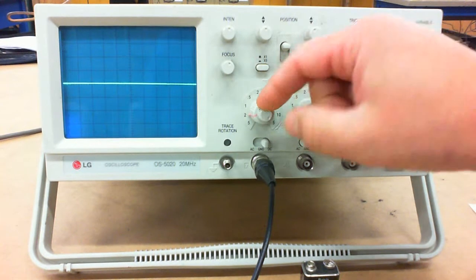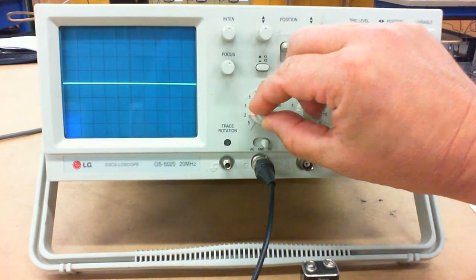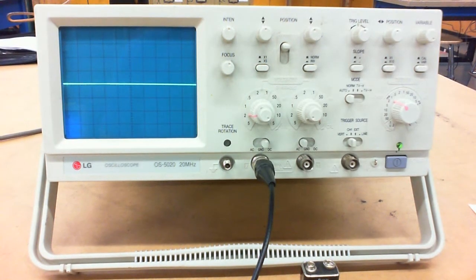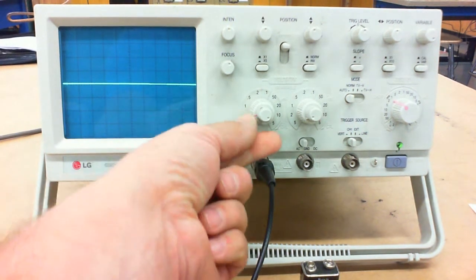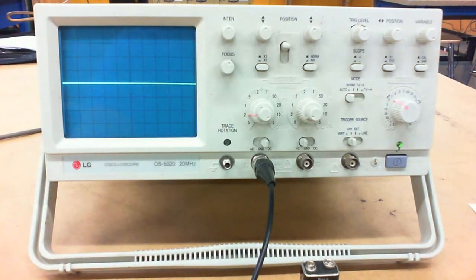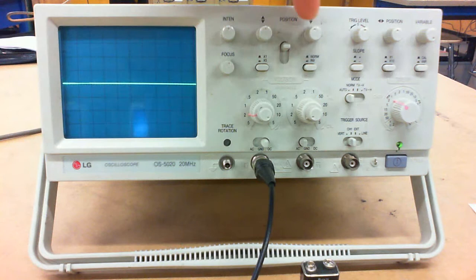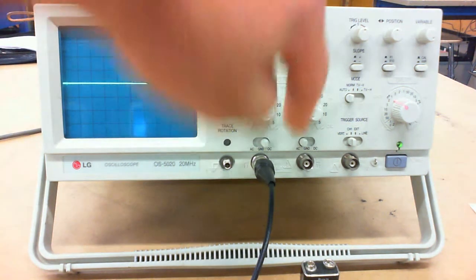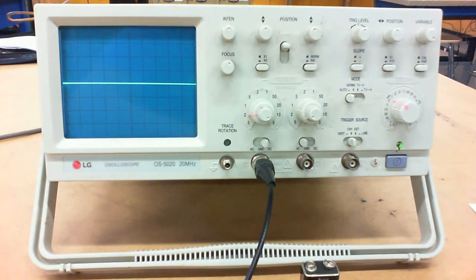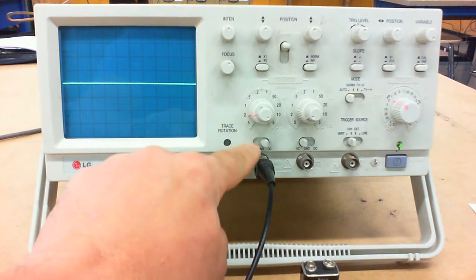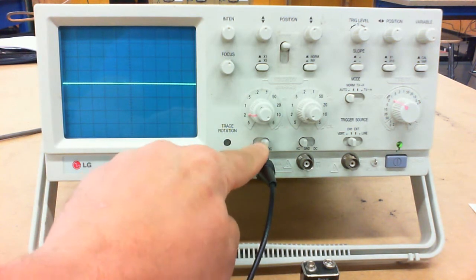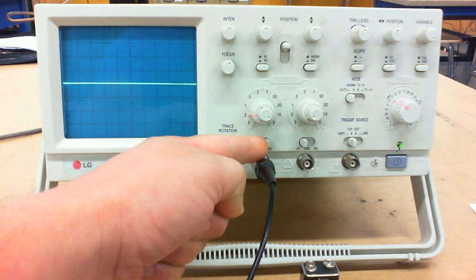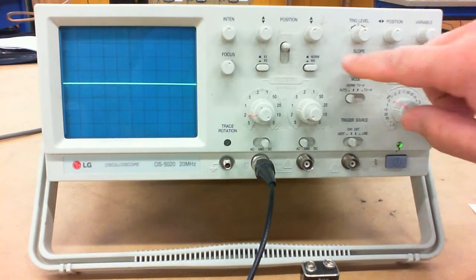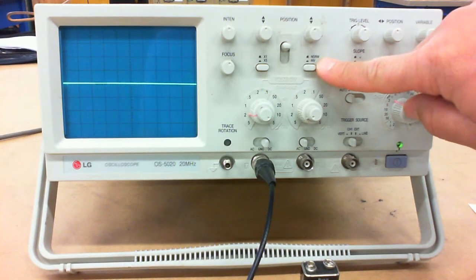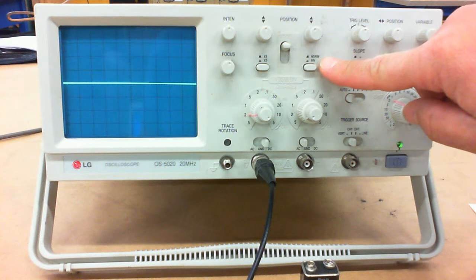The last thing on here is this variable knob has to be clockwise, and that just basically gives me my maximum voltage setting. So you need to ensure that is all the way up, otherwise you don't get the correct voltage readings. This is channel 2, which we won't worry about because we're only testing one channel. On here I've got AC and DC. I'm going to check DC, so it's over to DC. I have this normal invert. I want to make sure normal is depressed, so it's not pressed in.